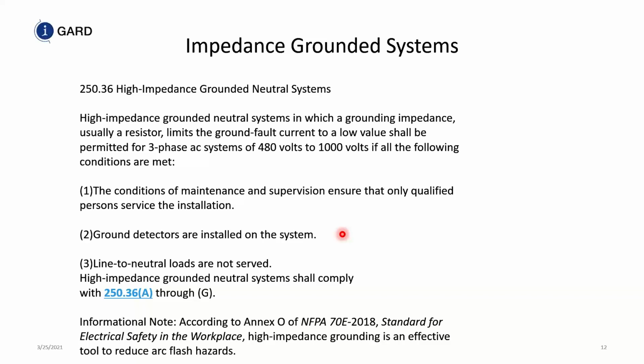Another important factor is they put an information note in NFPA 70, the National Electrical Code. It says, according to Annex O of NFPA 70E 2018, Standard for Electrical Safety in the Workplace, high impedance grounding is an effective tool to reduce arc flash hazards. So it's very important that they put that in there, because now you know that you can employ a high resistance grounding system. It doesn't necessarily say you need to interrupt the service if you have a ground fault.